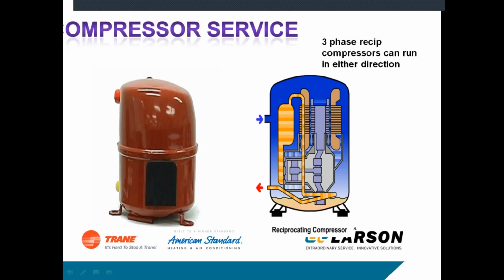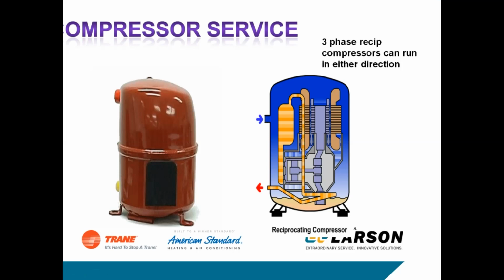The nice thing about the recip compressors is they were not polarity sensitive. Three-phase compressors could run backward or forward. It didn't really matter because it was just a crankshaft turning with a piston. So as far as the piston knew, it didn't really care which direction the shaft was turning.